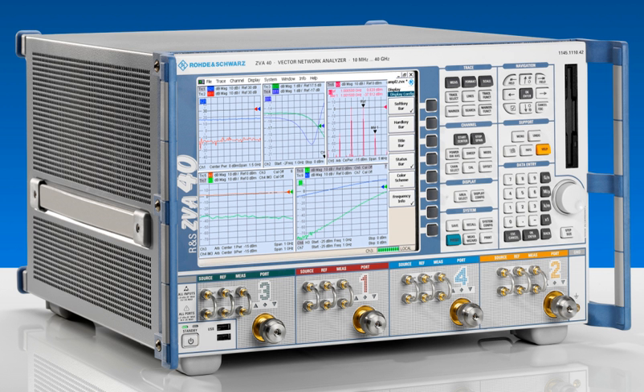Topic: automated calibration fixtures. A calibration using a mechanical calibration kit may take a significant amount of time. Not only must the operator sweep through all the frequencies of interest, but the operator must also disconnect and reconnect the various standards, Keysight Technologies 2003, p. 9. To avoid that work, network analyzers can employ automated calibration standards. Keysight Technologies 2003. The operator connects one box to the network analyzer. The box has a set of standards inside and some switches that have already been characterized. The network analyzer can read the characterization and control the configuration using a digital bus such as USB.